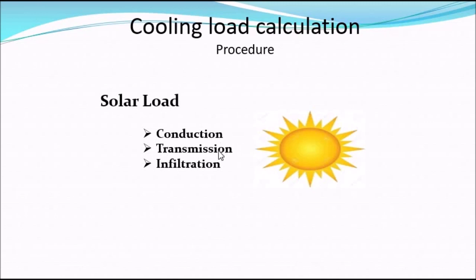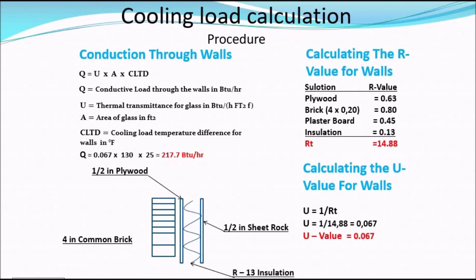In this example, due to a small amount of infiltration, we are only going to calculate the conduction and transmission load through the wall and glass. To calculate the conduction load through the walls, we use the equation Q = U × A × CLTD, where Q is the conductive load through the walls, U is the thermal transmittance, A is the area in square feet, and CLTD is the cooling load temperature difference for walls.